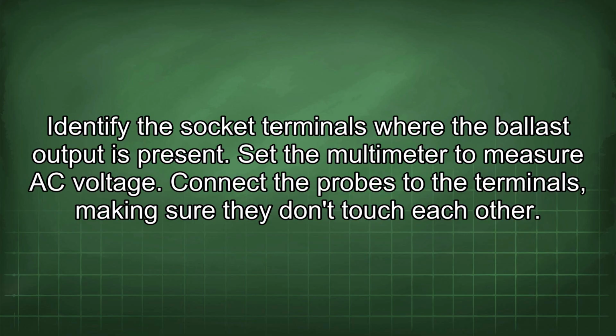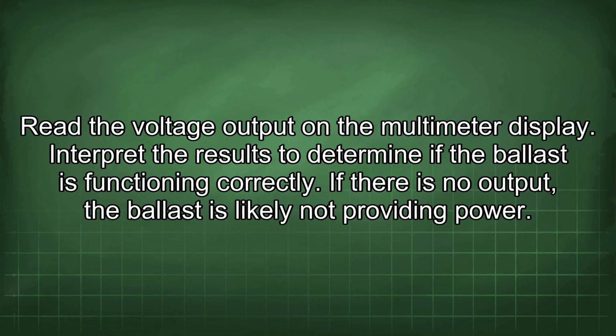Identify the socket terminals where the ballast output is present. Set the multimeter to measure AC voltage. Connect the probes to the terminals, making sure they don't touch each other. Read the voltage output on the multimeter display. Interpret the results to determine if the ballast is functioning correctly.